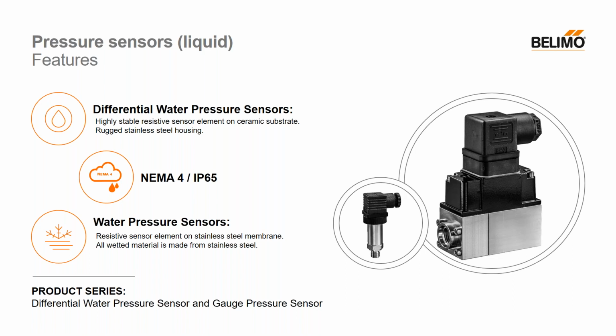This is a very basic analog output offering, no communication associated with the differential liquid pressure sensors or absolute liquid pressure sensor, but a standard, robust, very competitively priced DP and absolute or gauge pressure sensor. Again, the gauge pressure sensor can be used with water or refrigerant, while the differential pressure sensor is strictly designed for water side applications.